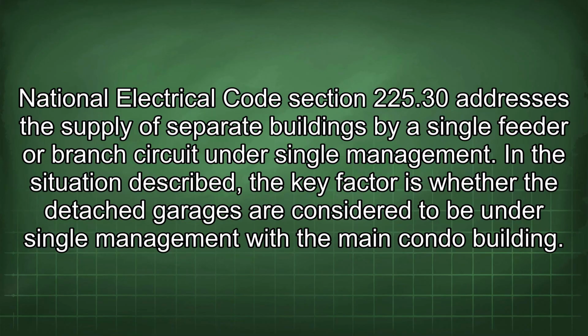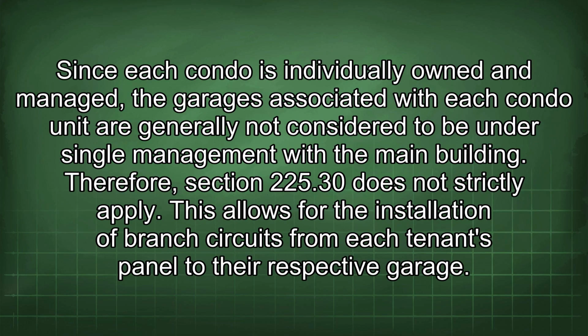National Electrical Code Section 225.30 addresses the supply of separate buildings by a single feeder or branch circuit under single management. In the situation described, the key factor is whether the detached garages are considered to be under single management with the main condo building. Since each condo is individually owned and managed, the garages associated with each condo unit are generally not considered to be under single management with the main building.